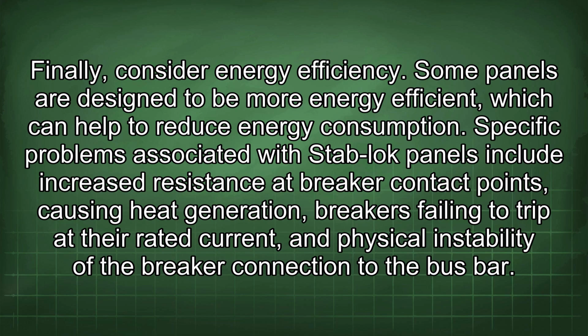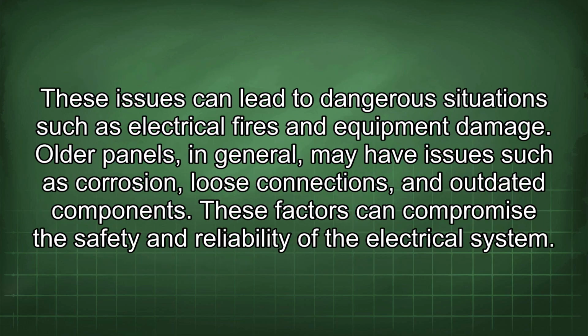Specific problems associated with Stab-lok panels include increased resistance at breaker contact points, causing heat generation, breakers failing to trip at their rated current, and physical instability of the breaker connection to the bus bar. These issues can lead to dangerous situations such as electrical fires and equipment damage.